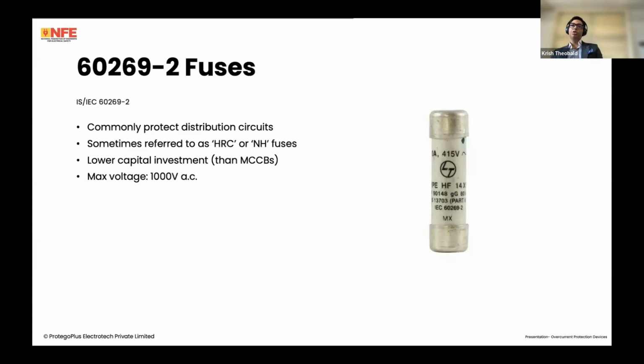The maximum voltage that these come in is 1000 volts AC. This is just for AC, obviously, because 60269 applies to AC. And like I said, there's no flexibility compared to your molded case circuit breakers because you cannot set up adjustable tripping curves. There are no time delays possible. You cannot set any time delays on a specific fuse. You require a different fuse altogether.